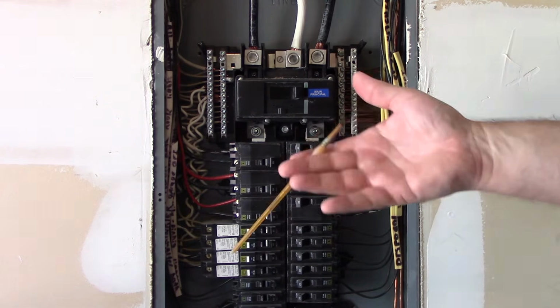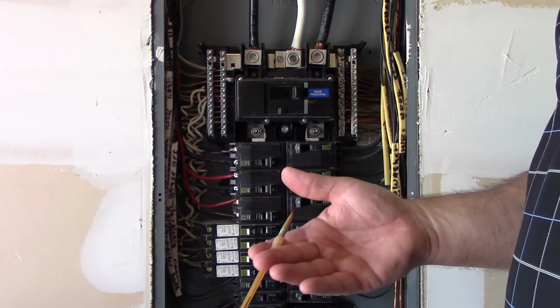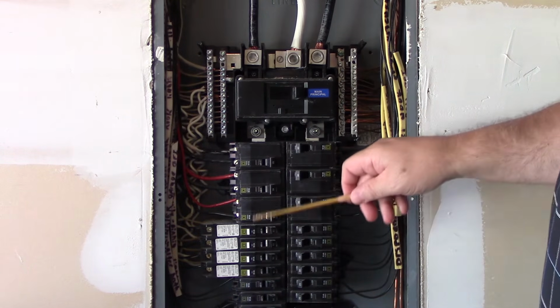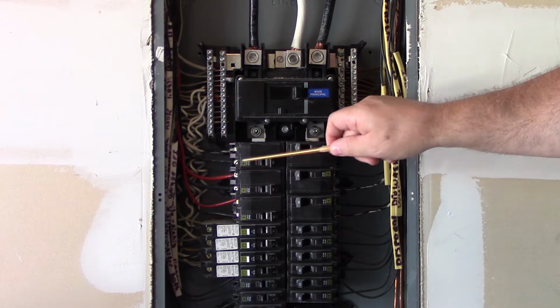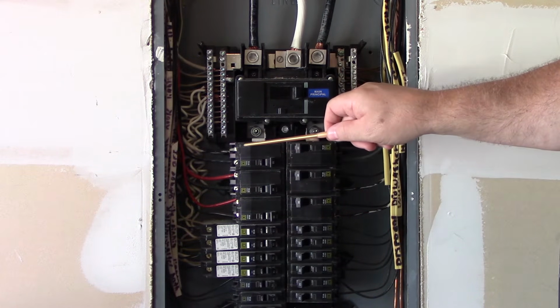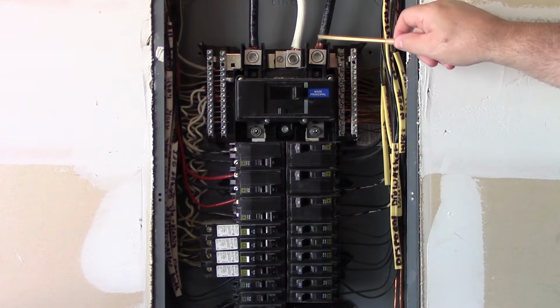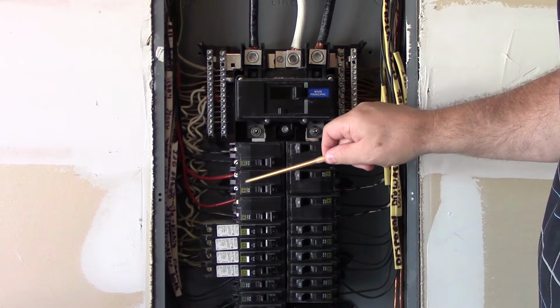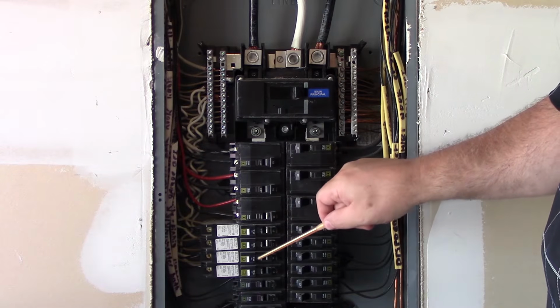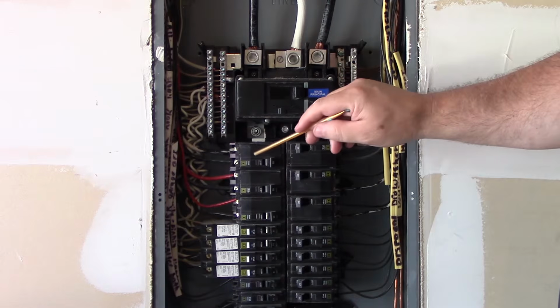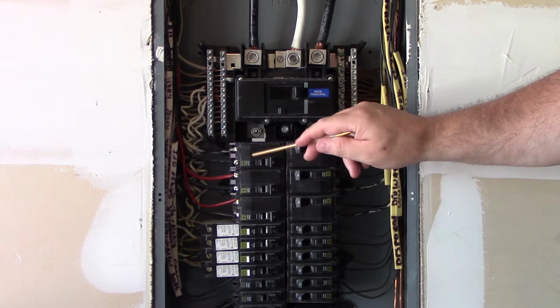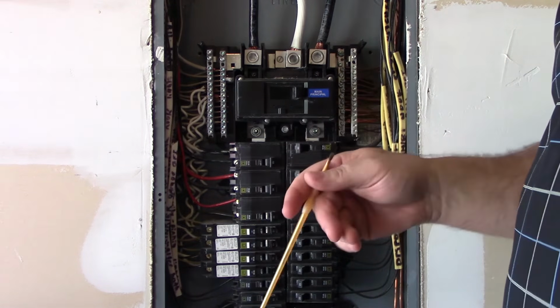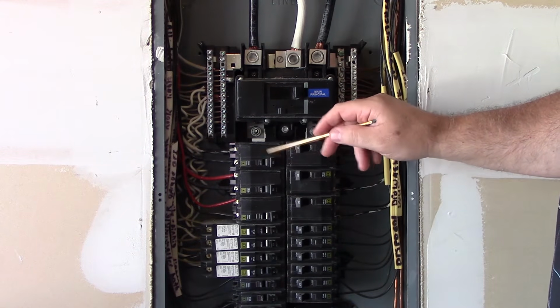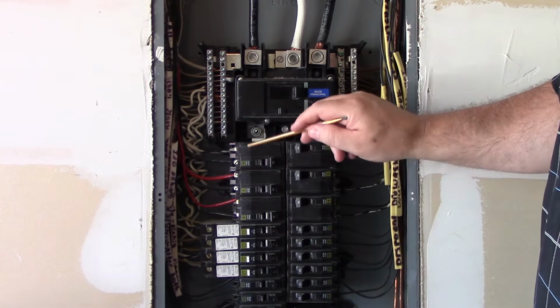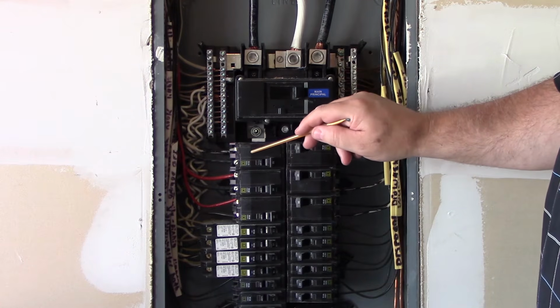Now, we talked about earlier a multi-wire branch circuit. In case you're one of those home inspectors that run into multi-wire branch circuits, one thing to remember is that as you go down this bar, it alternates. So this is A and this is B. You have A, B, A, B, A, B, all the way down. So it alternates. Now, if I install two single-pole breakers for use in a multi-wire branch circuit, which the National Electrical Code permits me to do, and I use an identified handle tie to bring them together, then the one thing I want to be aware of is that there's an A leg and a B leg.